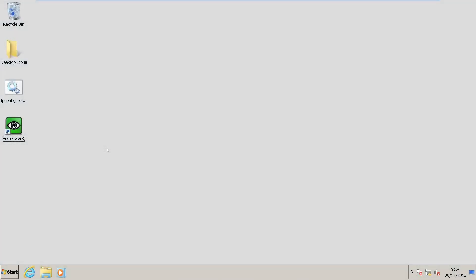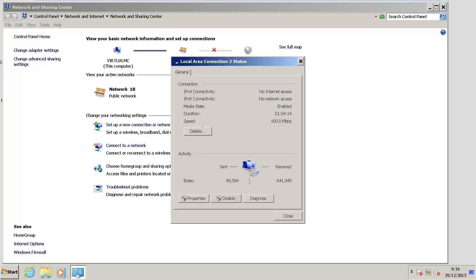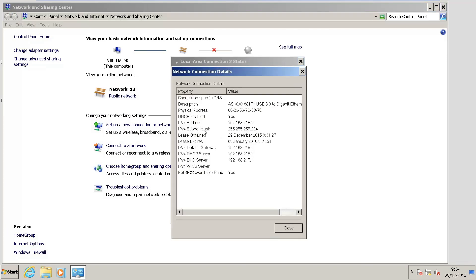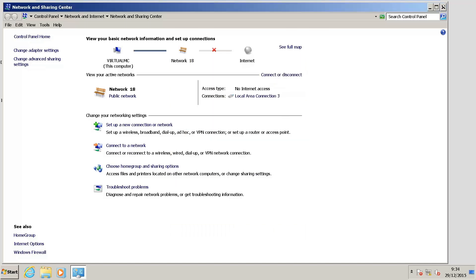So first you'll notice that I have a LAN connection with my computer, Local Area Connection number 3. I'm looking in my Network and Sharing Center. If I click on the Local Area Connection and the Details, I'll see that I have DHCP enabled and my address is 192.168.215.2. You want to have the .2 address because the control is a .1. The 192.168.215 address is assigned from the control to the computer. Now that I've checked that my properties are correct...